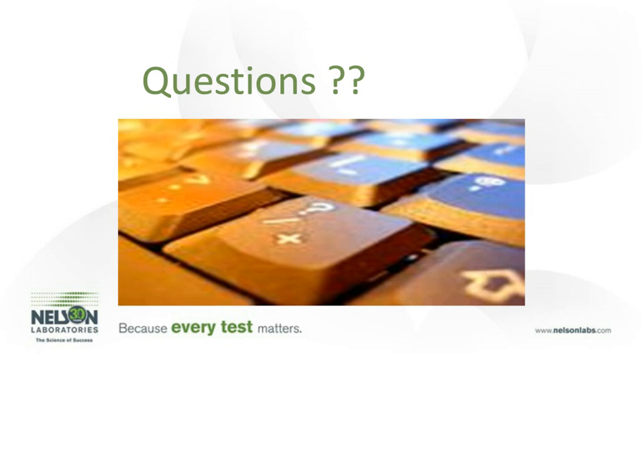Allison, I have a question for you. Is direct mark UDI required for single-use implants, that is, devices not intended to be used more than once? The questioner specifies devices intended for use or reprocessing repeatedly as part of an instrument case or set until consumed, such as spinal implants contained within the instrument set. Sure. As the draft document is currently laid out, that is one of the exceptions. FDA is saying that the direct marking requirements will not apply to devices that the manufacturer intends for only one use, or for use in a single patient during a single procedure, even if the device itself is processed multiple times before the single use on that patient.